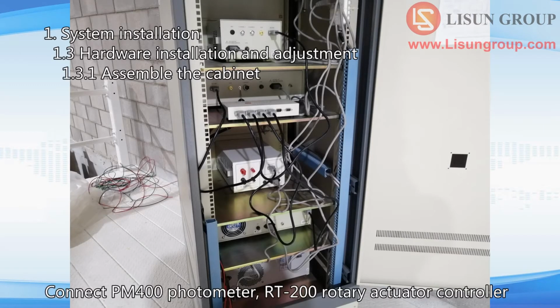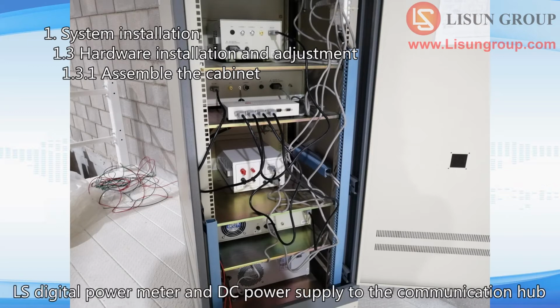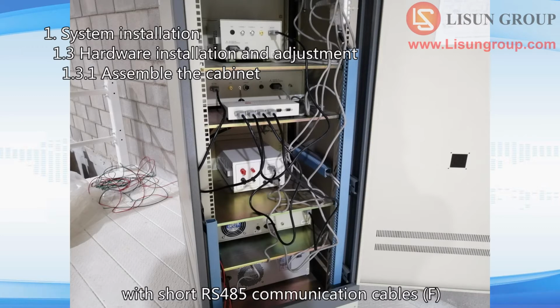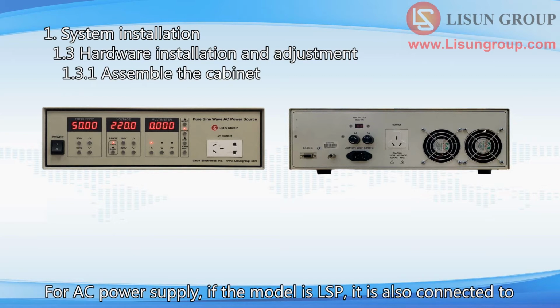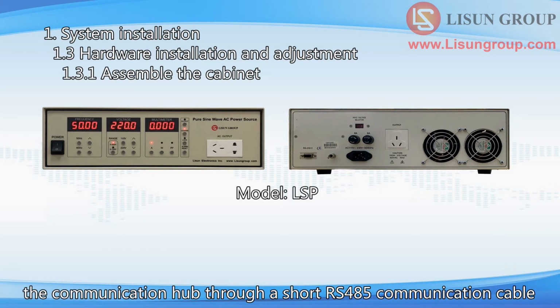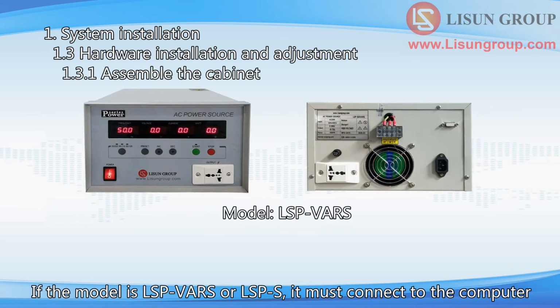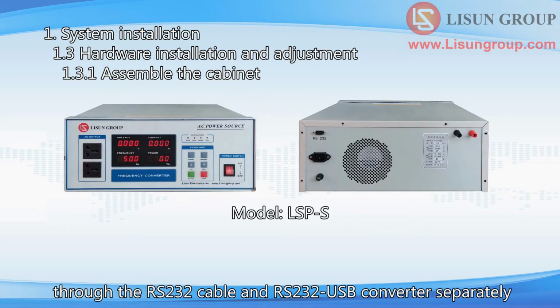Connect the PM400 photometer, RT200 rotary actuator controller, LS digital power meter and DC power supply to the communication hub with short RS-485 communication cables. For the AC power supply, if the model is LSP, it is also connected to the communication hub through a short RS-485 communication cable. If the model is LSP-VARS or LSP-S, it must connect to the computer through the RS-232 cable and RS-232 USB converter separately.